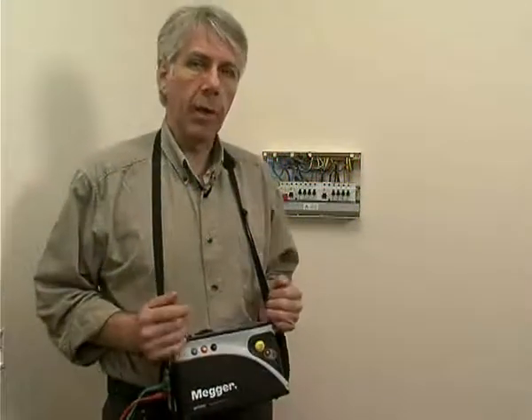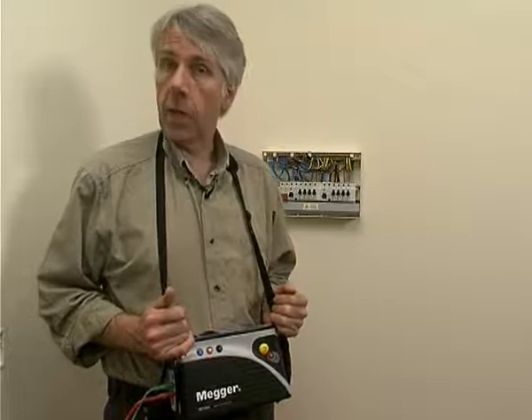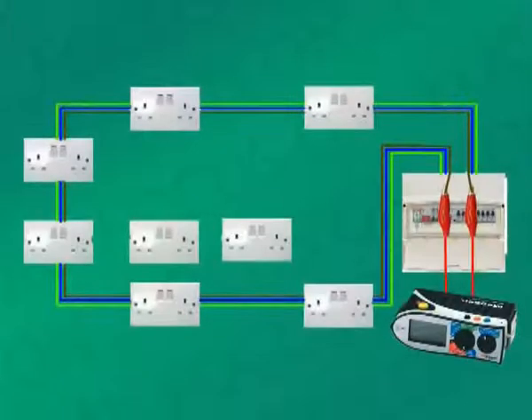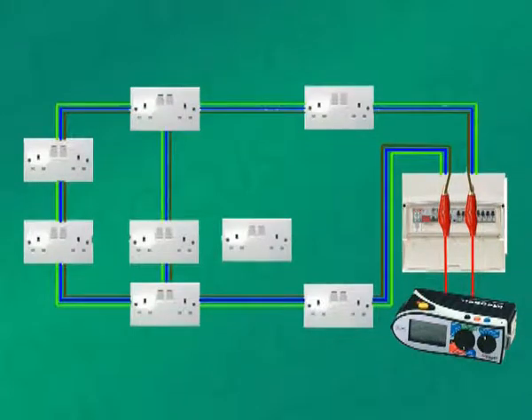We've explained the test procedure and what can cause readings to vary. The other thing we need to consider is when ring final circuits have bridges or interconnections and how this will affect readings. Here's our diagram of a normal ring final circuit. A bridge would be a connection which might do this, bridging from one side to the other, usually supplying one or more socket outlets on the way.